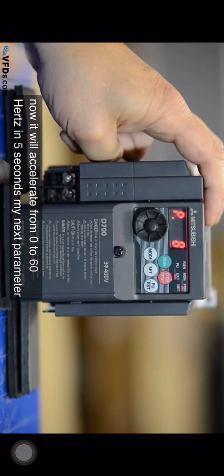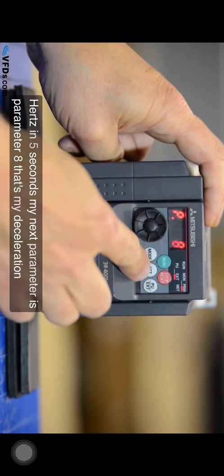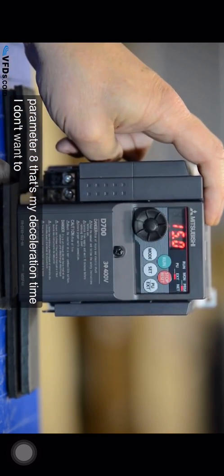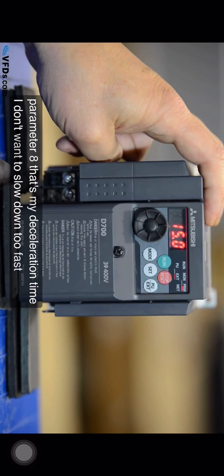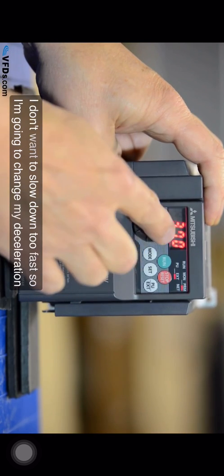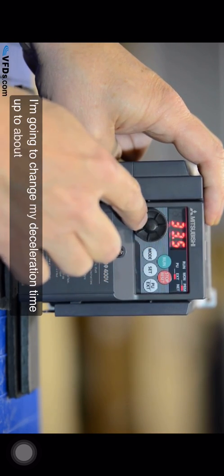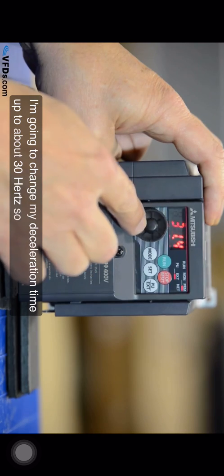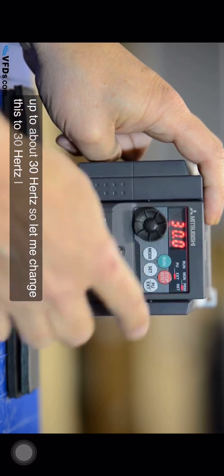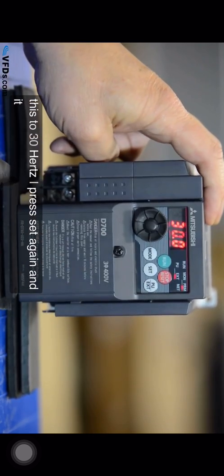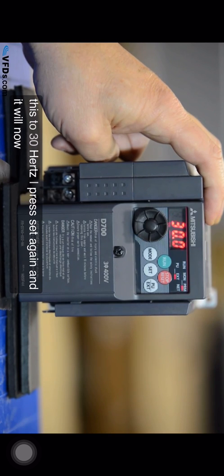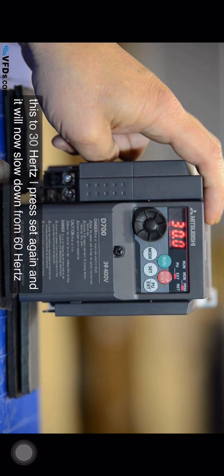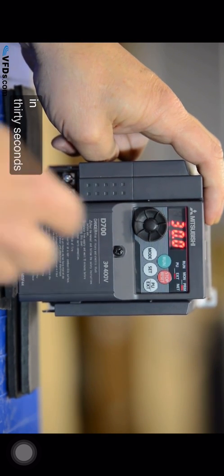My next parameter is parameter eight. That's my deceleration time. I don't want to slow down too fast so I'm going to change my deceleration time up to about 30 seconds. So let me change this to 30. I press set again and it will now slow down from 60 hertz to zero in 30 seconds.